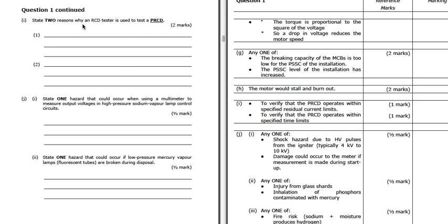I, two reasons why an RCD tester is used to test a PRCD. So what are the two things that we're testing when we're testing this? We're testing that it operates within the specified residual current limits, be that 10 milliamps or 30 milliamps or 100 milliamps. We're verifying that it operates within the specified time limits. So we're looking at the maximum current, the sensitivity, and the time.